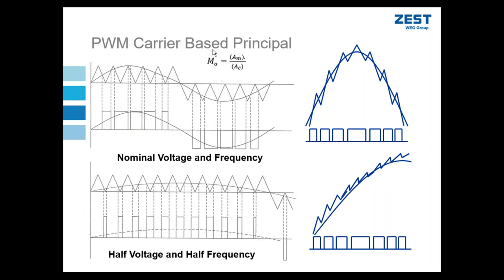Okay. Another term that we want to define here is modulation index. So when I supply 50 hertz to a machine, I also want my voltage to be at its maximum. Why? Because a VSD increases voltage from zero to nominal in linear scale with the increase in speed. So in other words, if I supply, for example, 6,600 volt from the VSD to a machine at 50 hertz, when the VSD supplies 25 hertz, it also reduces the voltage amplitude to 3.3 kV, half. So we have a linear relationship between the output voltage and the output frequency.